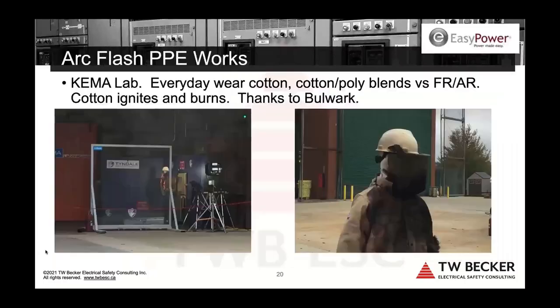Now, arc flash PPE works. I've been lucky enough to get to both Kinetrics with Oberon and KEMA with Bulwark. And this is Bulwark at KEMA in Pennsylvania. What you see on the screen is the test apparatus on the left, and on the right, the outcome. That's a pass. You see this carbonization of the shield and of the actual arc rated garment. It works. We just need to get the workers to wear it, and wear it religiously when they're exposed. So I'm going to show a video.